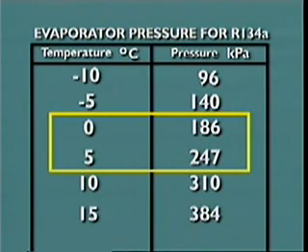This difference in temperature is called superheat and it ensures that all liquid refrigerant which enters the evaporator is vaporized before it leaves.